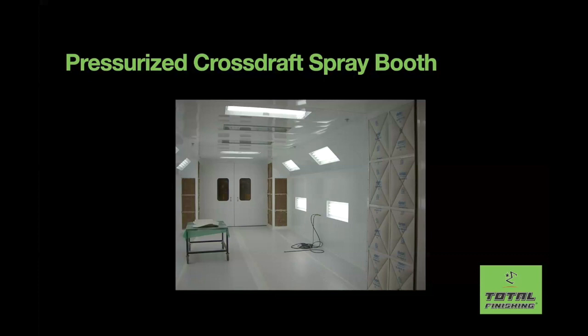Very directional, yes. So this is the least expensive way to move the required amount of airflow, because you only need one fan, and the cross section of how you come up with the CFM is the narrowest. But you are dragging your own overspray across your own parts. Makes sense. So a downdraft would be better then, I guess. Correct. Yep. So we're going to get into that.